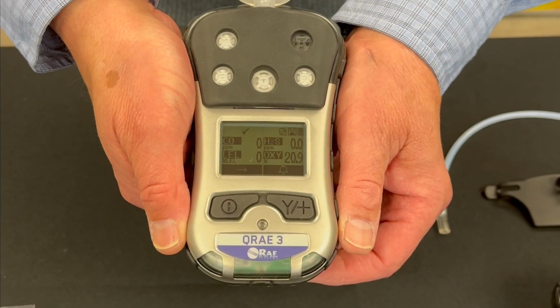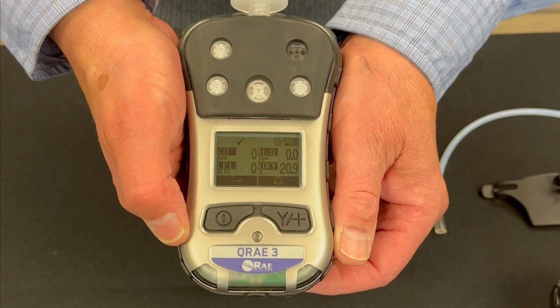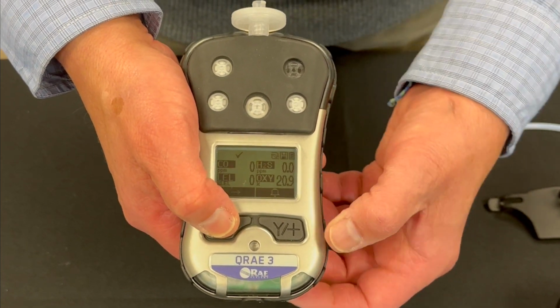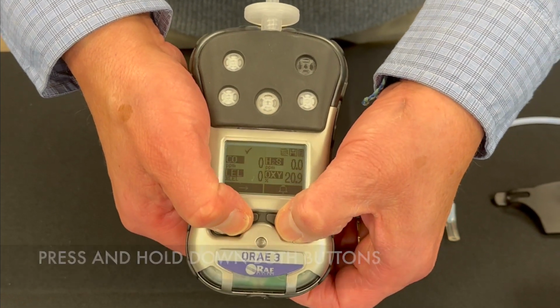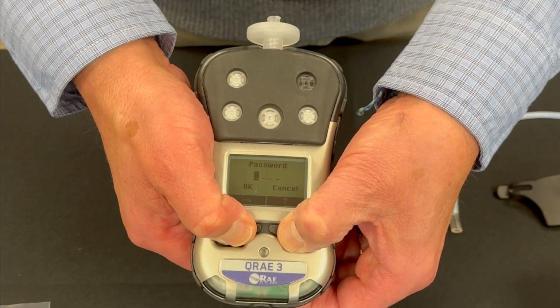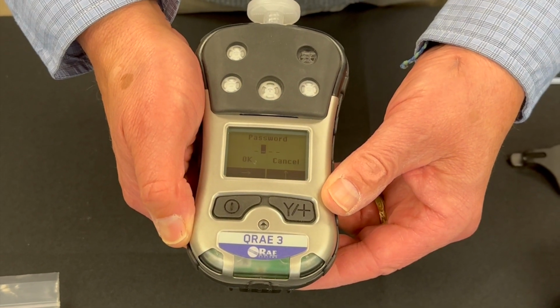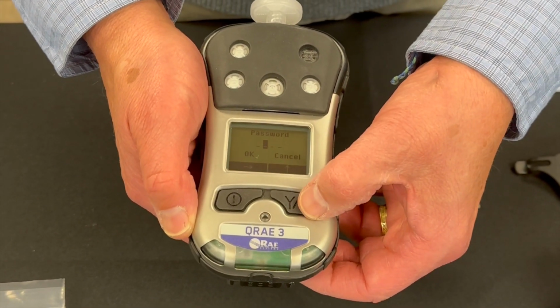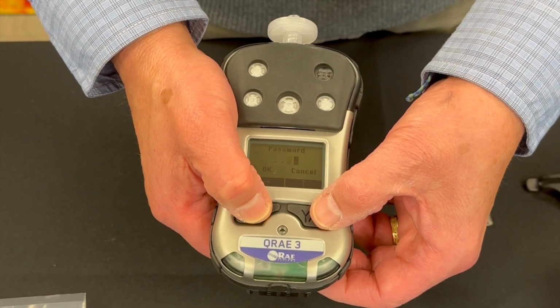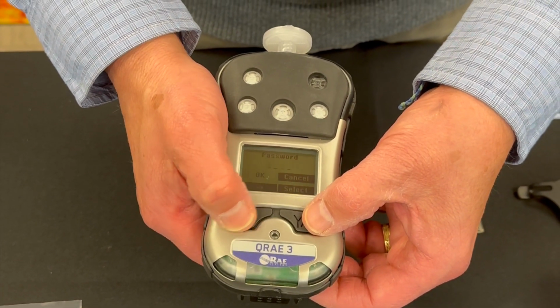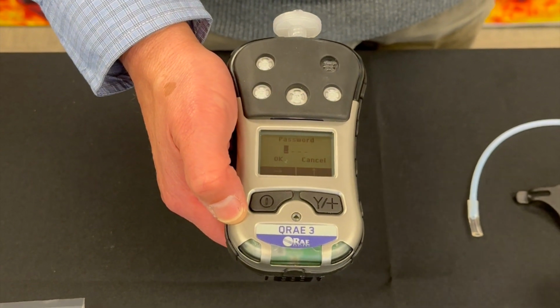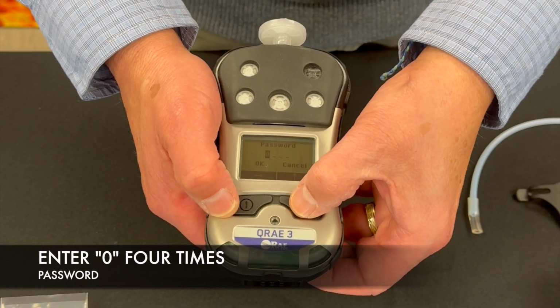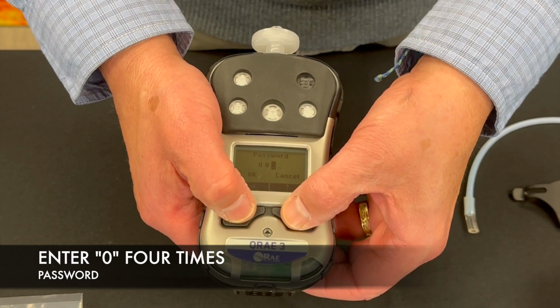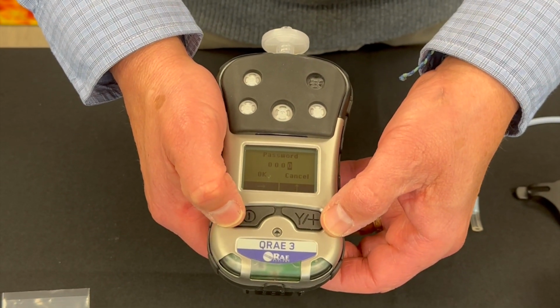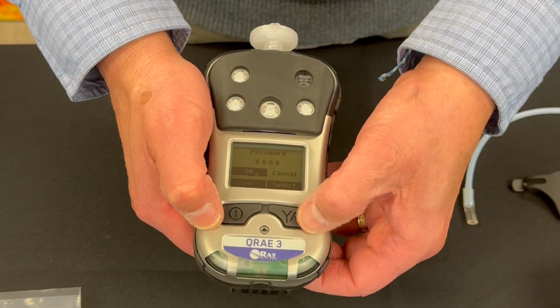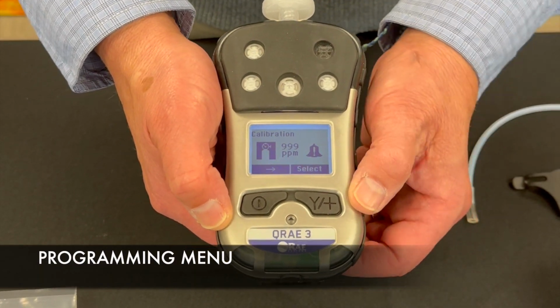To get into the calibration procedure, you depress both operating buttons at the same time, both the on-off button as well as the yes or enter button. I press and hold. I come up with a request for a password. The default password for all RAE Systems products in the QRAE series and multi-RAE series is zeros. I manipulate my buttons to get all 4 zeros. I hit the OK under Select. I'm now in my programming menu.